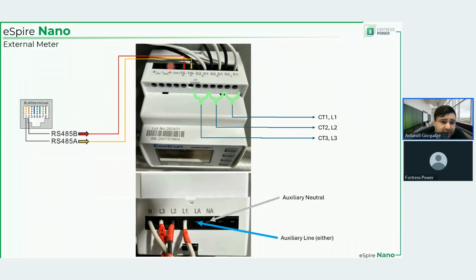So if you have an Ethernet cable that will connect the inverter to the meter, you will open the jacket, disable pins 3, 4, 5, 6, 7, and 8, so no signal can transmit there. On one end, you will have RJ45, and that will connect to the meter port. And on the other end, you will have wires for pin 1 and pin 2, with an exposed conductor, connecting to TXB minus and TXA plus ports.